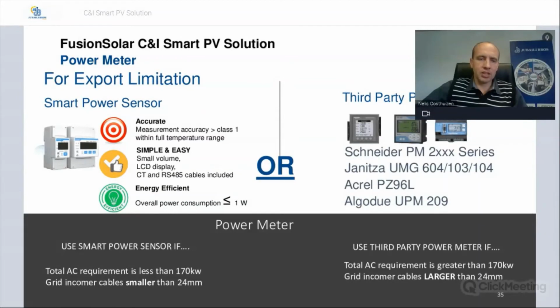Then, as I've mentioned before, these power sensors are only applicable to the smaller side of the C&I solutions. Total AC requirement is less than 170 kilowatt. Grid incoming cables should be smaller than 25 millimeters. Then if your systems are bigger than 170 kilowatt, we would advise the use of third-party power meters.